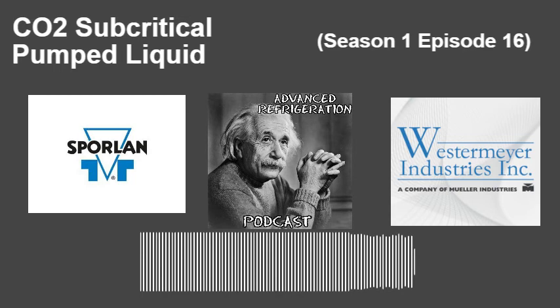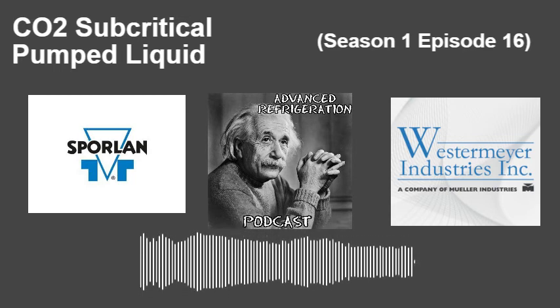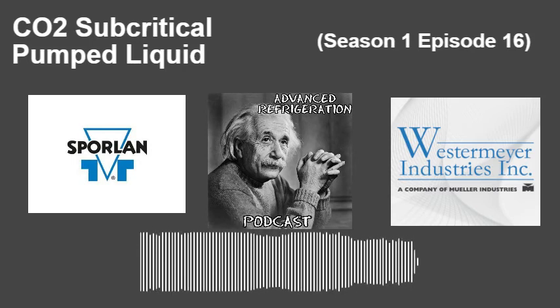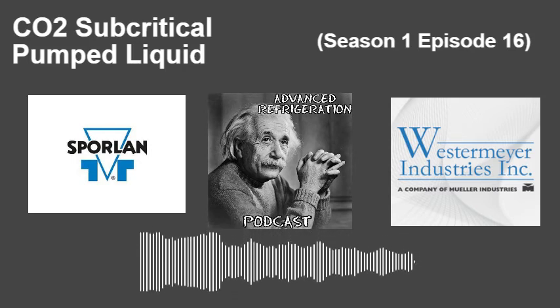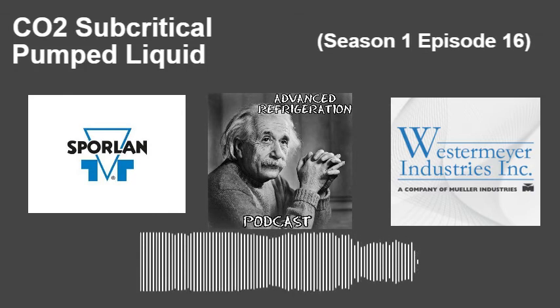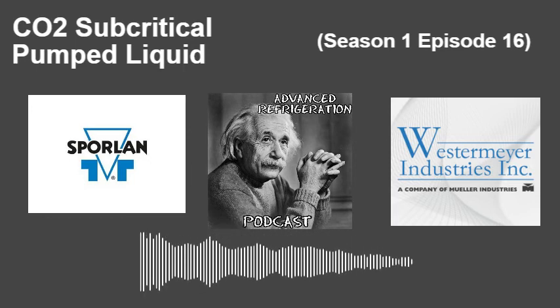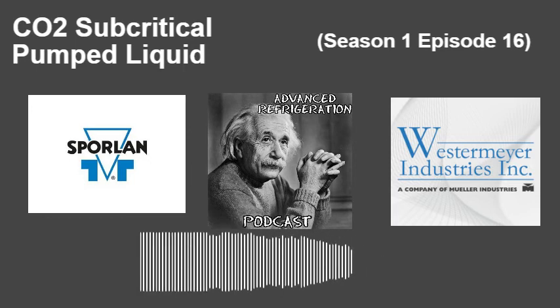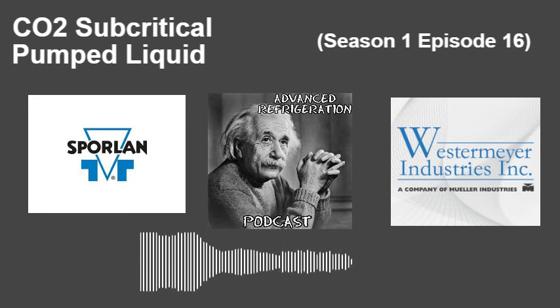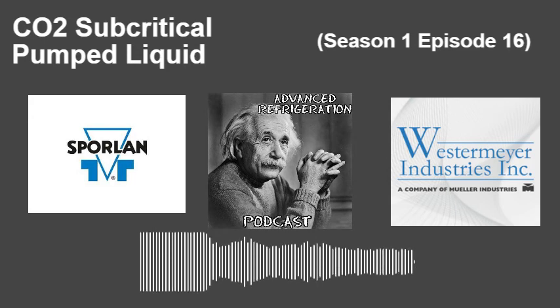I've seen a bunch of Cascade racks that have auxiliary side condensers, basically another heat exchanger, in case you have a failure on the DX side. Have you ever seen that on a pumped liquid system? I never have. No. There is a chain up here supposedly doing pumped liquid. I have yet to see one, but supposedly they're putting auxiliary units in.